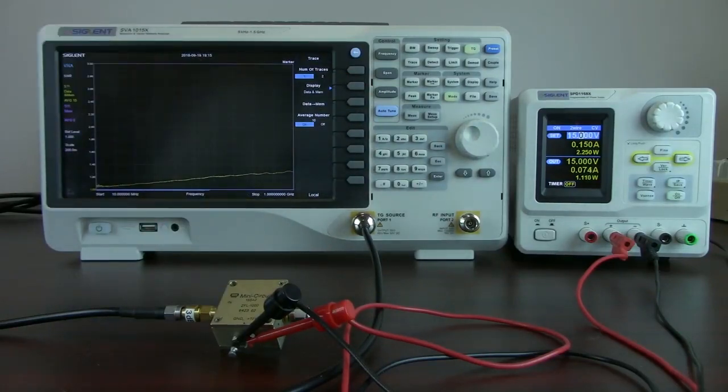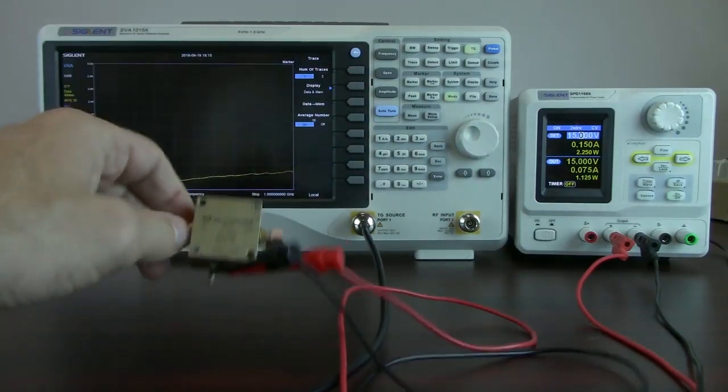I can save that into memory. So I can go data memory, and that's going to freeze that particular input curve for the VSWR. And now let's take a look at the output curve. So I'm simply going to disconnect the cabling from the input.